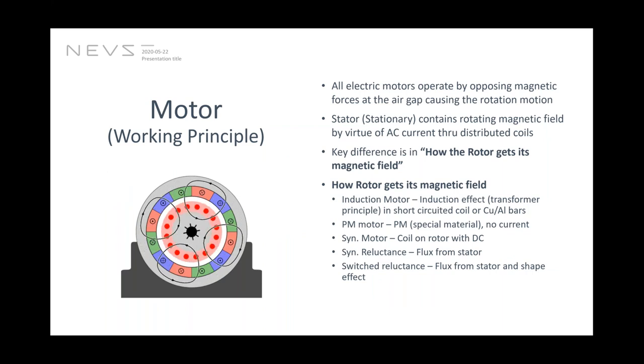So the next step is to discuss the working principle of the motor. In very, very basic terms, all electrical motors operate by opposing magnetic forces in the air gap. The stator is the stationary part which gets the rotating magnetic field by virtue of AC current in the distributed coils, as shown in the figure, as shown in the animation there. And the main difference in all the machine types is how you get the field in the rotor.